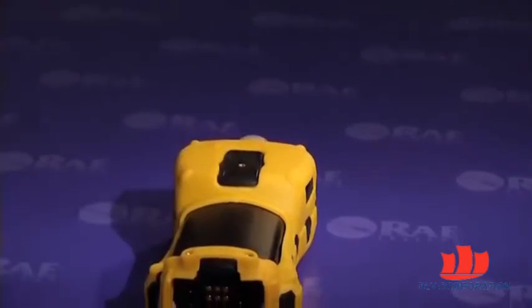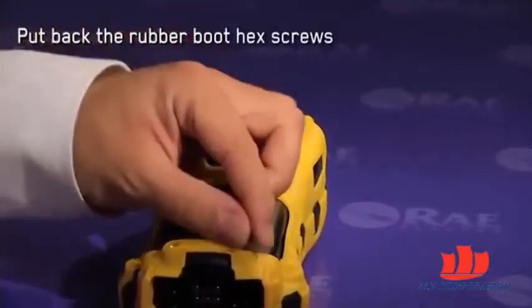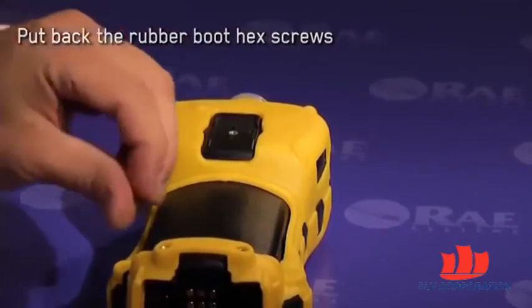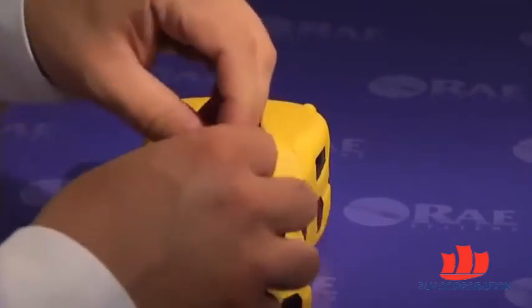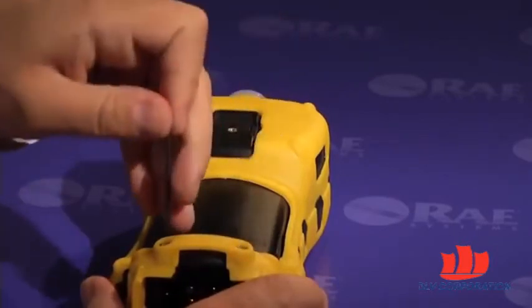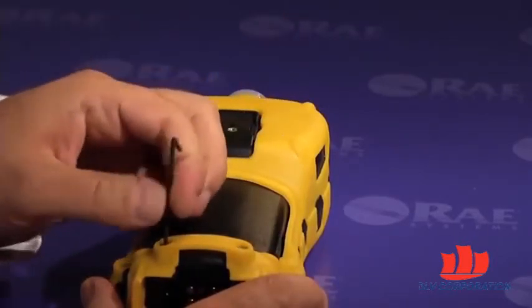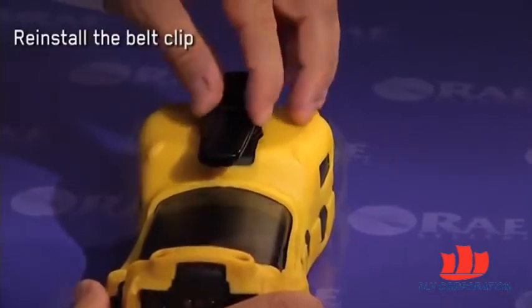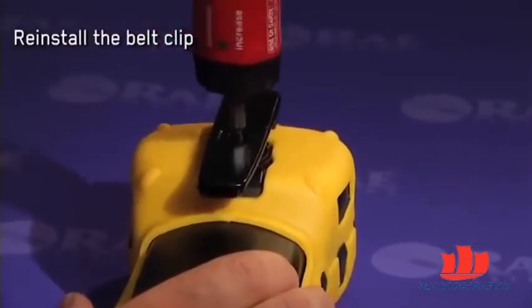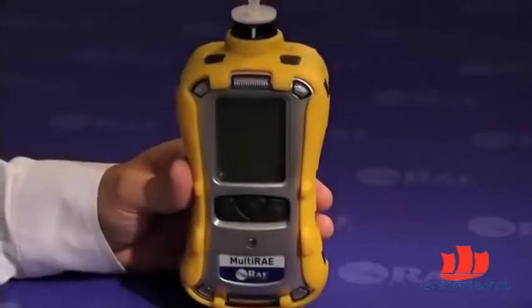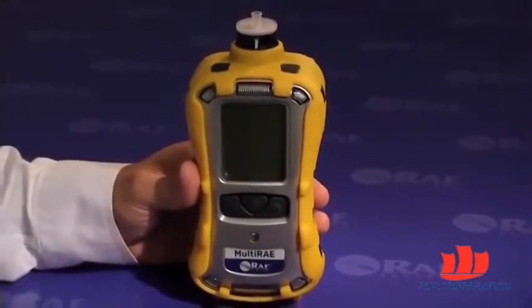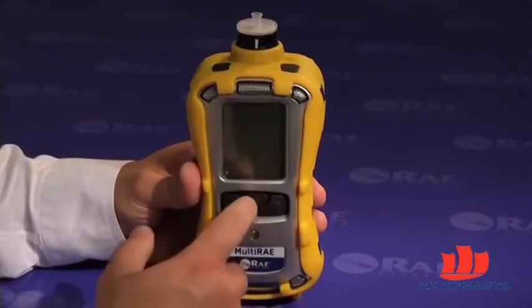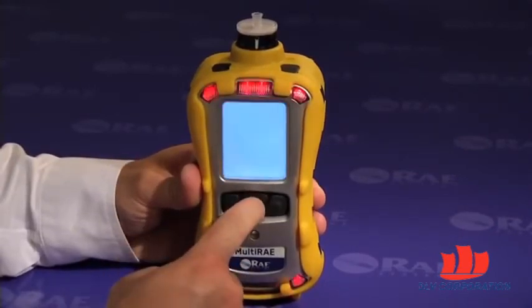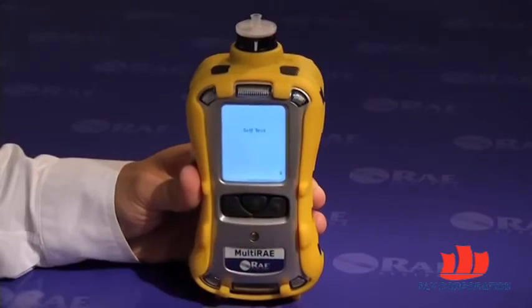It is a pretty easy process. Then we should reinstall the 2 hex screws that hold the rubber boot in place. We'll use the supplied hex tool to do so. And finally, the belt clip is the only one that's left to be reinstalled. The sensor replacement process is now complete. It is advisable to verify that the sensors are fully and properly seated in the sensor slot by turning the unit on. If you don't get a sensor error message on boot up, you've done a proper job of sensor replacement.